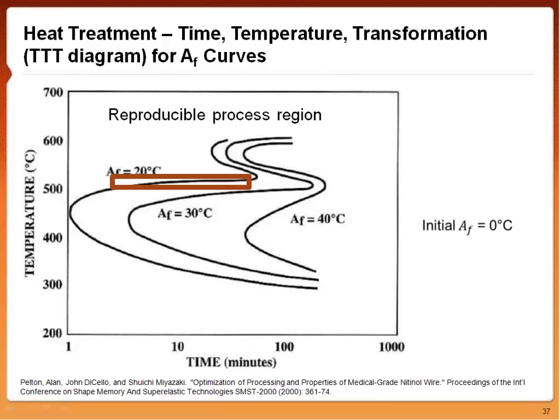Well, one of the options you have is you can choose maybe around 450 degrees Celsius for about a minute. However, the problem with that is you can see you're on a steep part of this curve. So your process is going to have a lot of variability if you think about it. You're going to take a piece of material, heat treat it, it's going to be warm, and you pull it out of the bath or whatever you're using to shape set it. It's going to cool off a little bit, and then it's going to quench. So it's actually experiencing a range of temperatures. So it's really hard to control that 450 degrees Celsius mark for that minute.